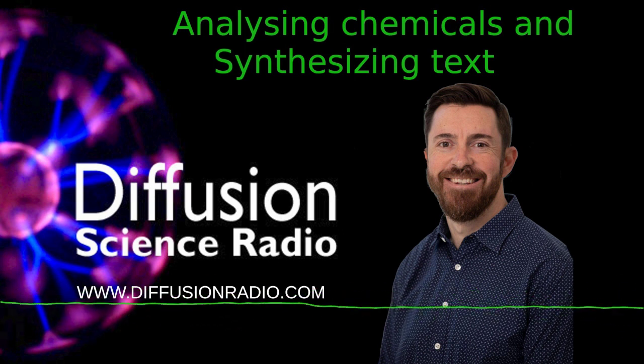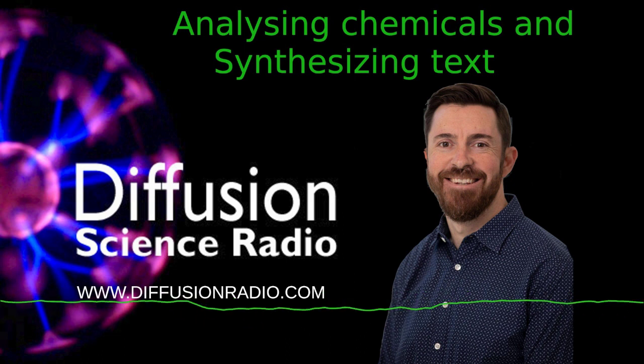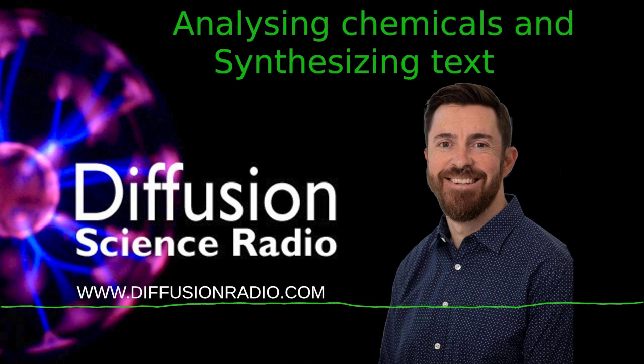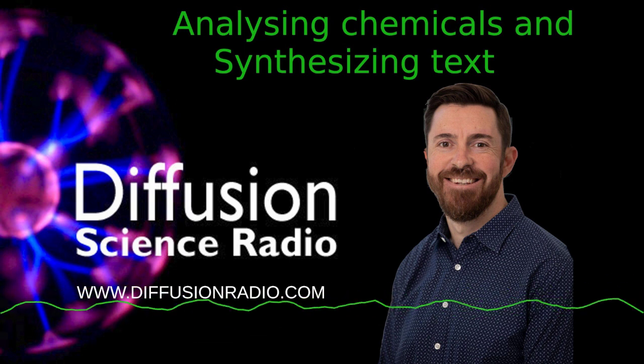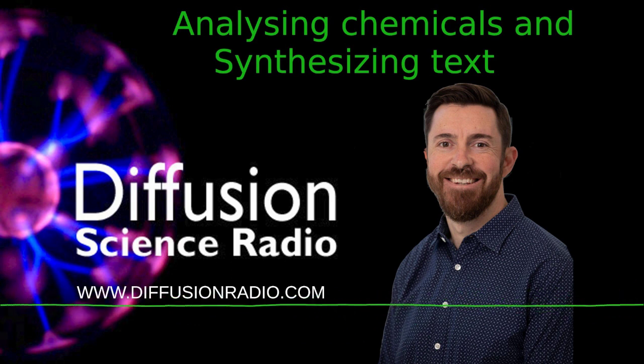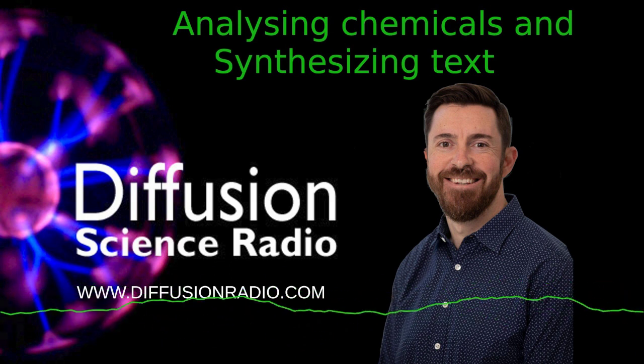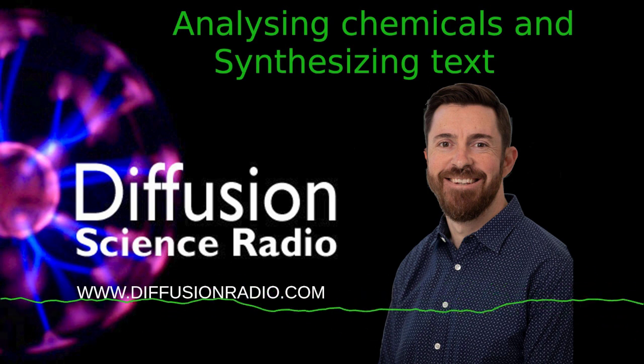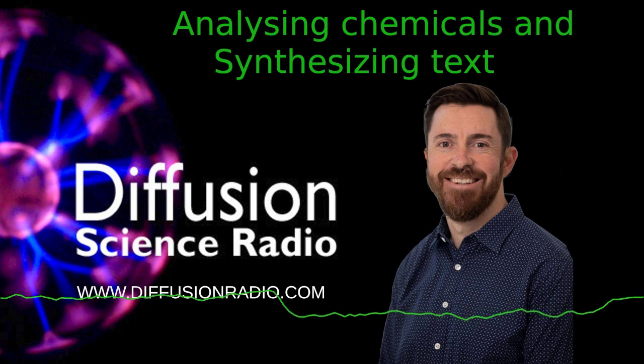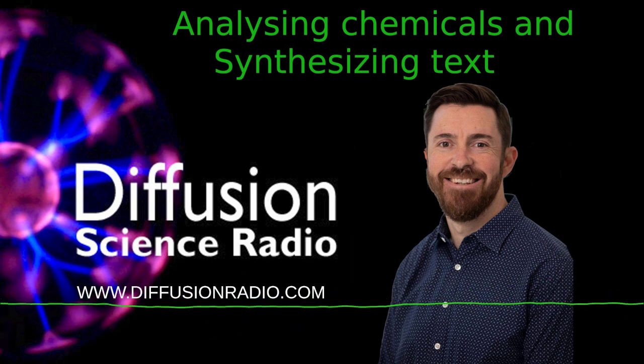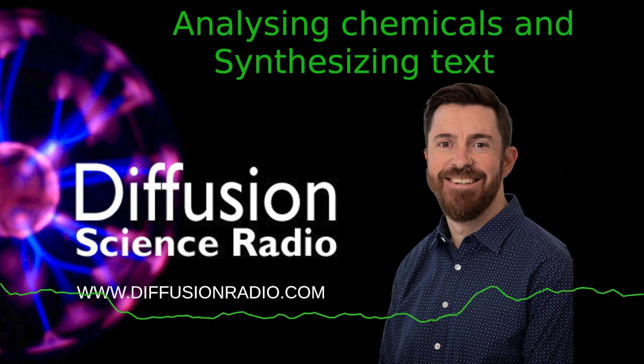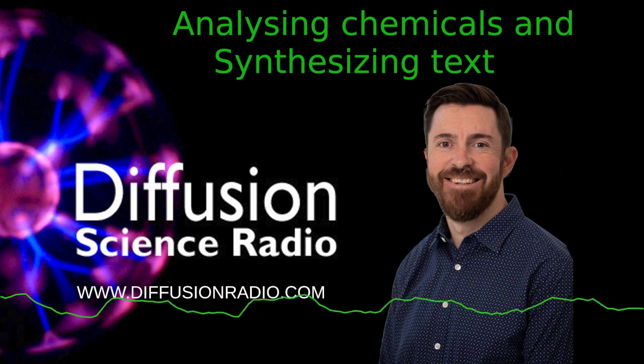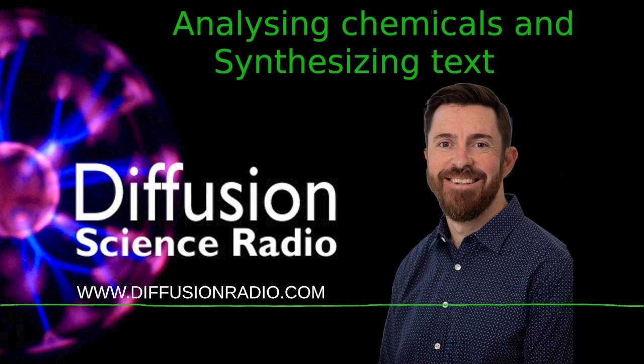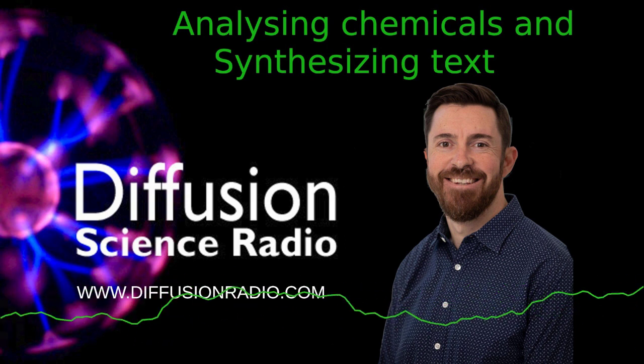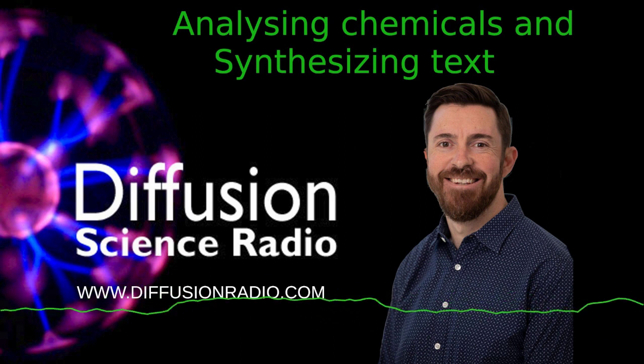The detector itself does not measure each metal ion itself. All it does is measure a signal coming through. So the analyzer is very important to separate out and only allow through one ion at a time. This is a very rapid process, and basically for each ion we're looking at, it can spend as little as 5 milliseconds ensuring that each individual ion goes through. But as I said, if we look at up to 40 elements at a single time, that is still a very rapid process and allows us to scan a number of times very, very rapidly so that we have some confidence in our data. So it sounds like it's going through everything in the sample once the water's gone.